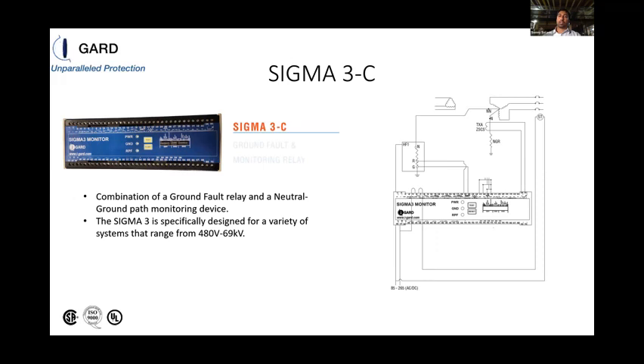When it comes to low resistance grounding, we're focused more on seeing whether that charging current is going to be greater than 10 amps, and whether your system is greater than 5 kV. In that case, we size our let-through current greater than our protection pickup at our feeder level, and then we have it as time rated and tripping on first fault.